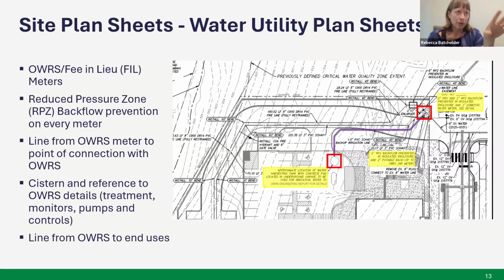I want to see that OWRS backup meter in most cases. I also need to see backflow prevention as required by your project—we'll get into what types of backflow prevention are required for different on-site water reuse projects in coming slides. But in most instances we require RPZ backflow prevention at all the meters on your project, and they need to be right downstream of the meter, unless you have special authorization to put them elsewhere. So I check to make sure those are there. A lot of my comments are just: I don't see your backflow, or you've used a double check valve assembly instead of an RPZ.